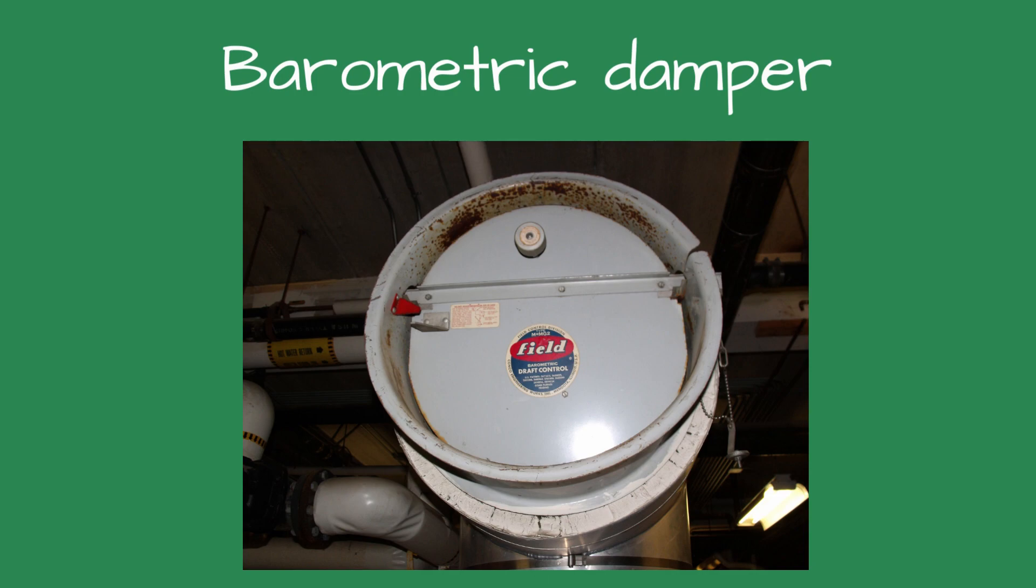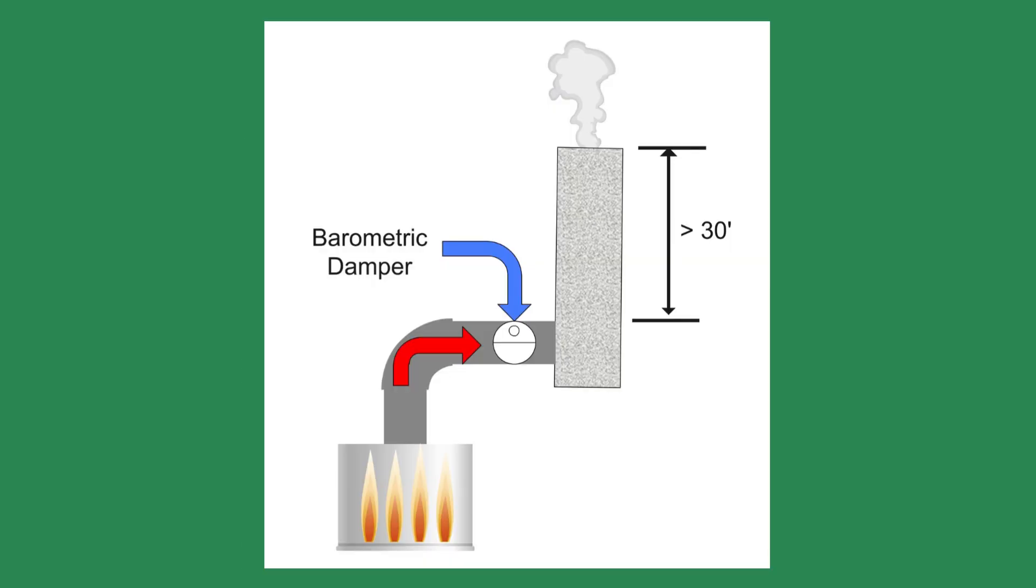Draft controls are recommended when the chimney or stack exceeds 30 feet, and a barometric damper is a common, cost-effective solution. The barometric damper is installed in the flue pipe between the boiler and the chimney. It is set for the desired draft conditions using weights and adjustment screws. If the chimney draft exceeds the set point, the damper will open and allow air from the boiler room inside the chimney rather than stealing heat from the boiler.